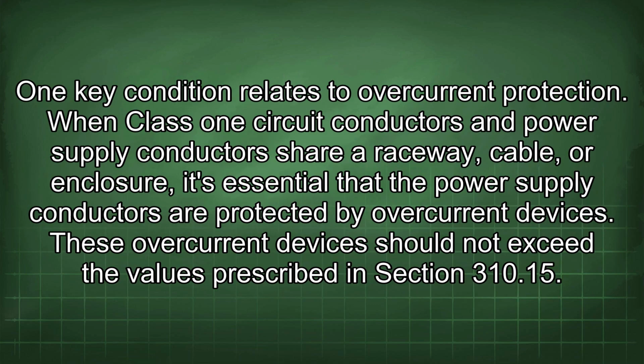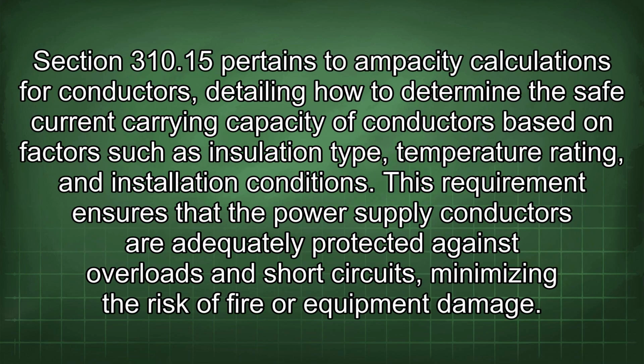One key condition relates to overcurrent protection. When Class 1 circuit conductors and power supply conductors share a raceway, cable, or enclosure, it's essential that the power supply conductors are protected by overcurrent devices. These overcurrent devices should not exceed the values prescribed in Section 310.15. Section 310.15 pertains to ampacity calculations for conductors, detailing how to determine the safe current carrying capacity of conductors based on factors such as insulation type, temperature rating, and installation conditions.